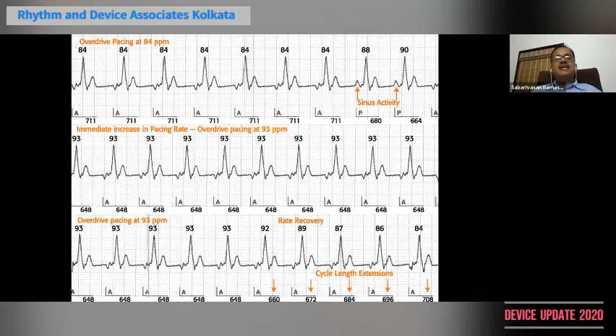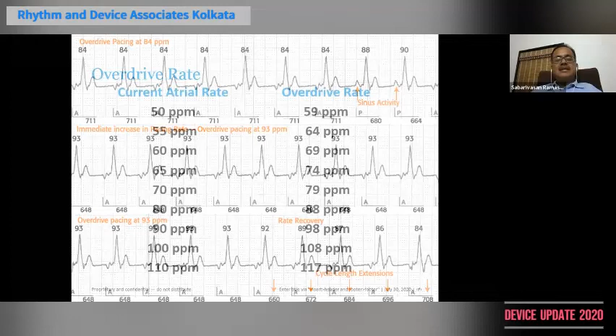So if the current atrial rate is around 50, it paces around 59. That is, in the base rate, it paces 10 beats above the sinus rate. And when it goes to the maximum tracking rate or the sensor rate, it goes 5 beats above. So in between, it will be more than 5 to 10 beats. So this is how it is always overdriving, always looking at the sinus. If the sinus goes up, immediately it increases the rate of the pacemaker.